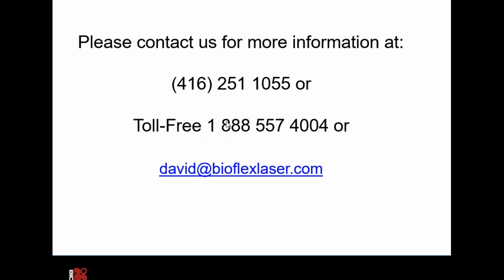So I have a question from Pam, and she says every body part is timed at 14 minutes. This is different than my first unit in which treatment times varied. Could you clarify? Okay, so there were some modifications or adjustments to some of the protocols over the generations of the equipment that we were manufacturing. Some of that reflected in the changing of the energy densities as well.